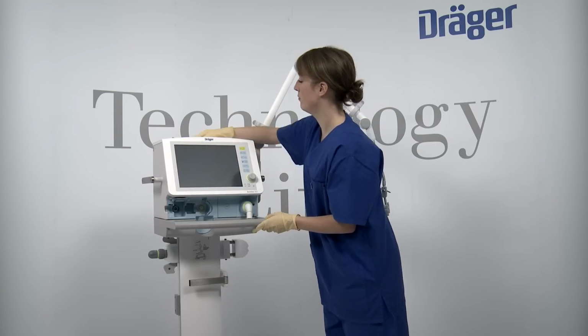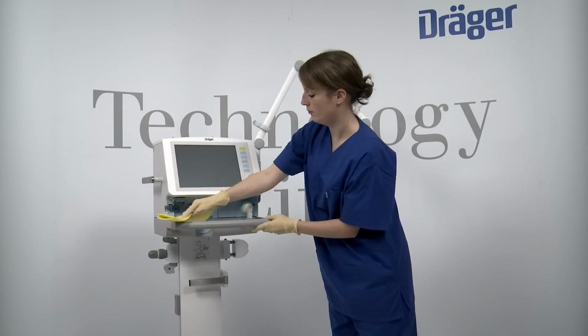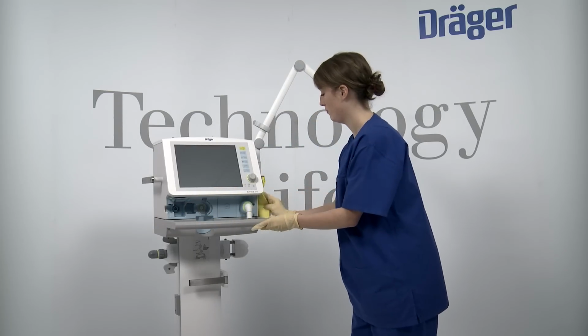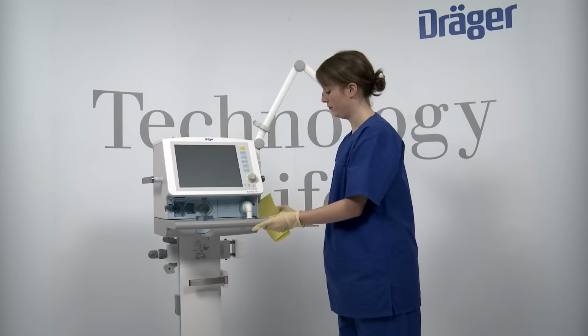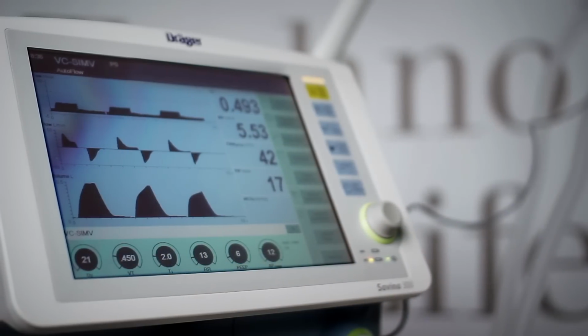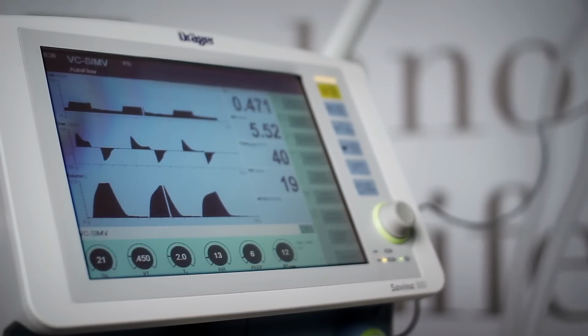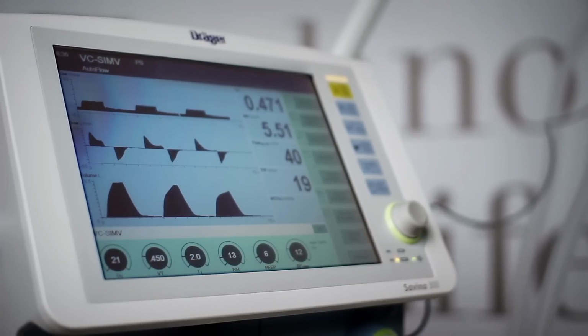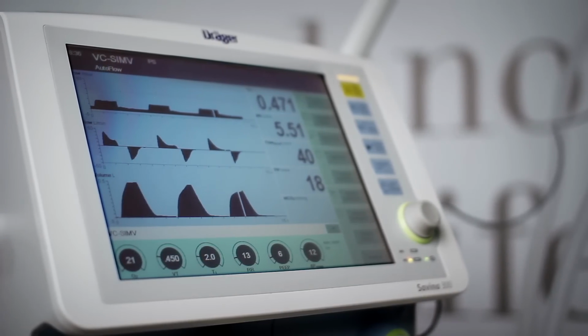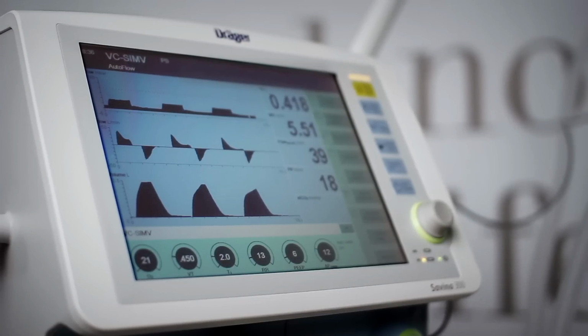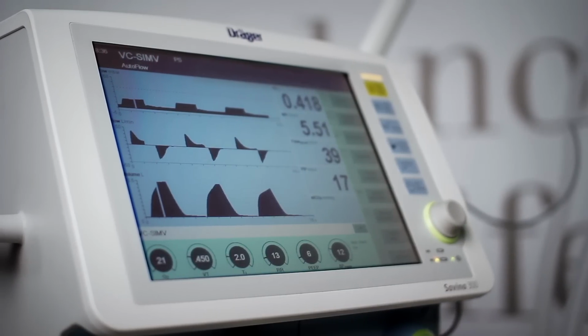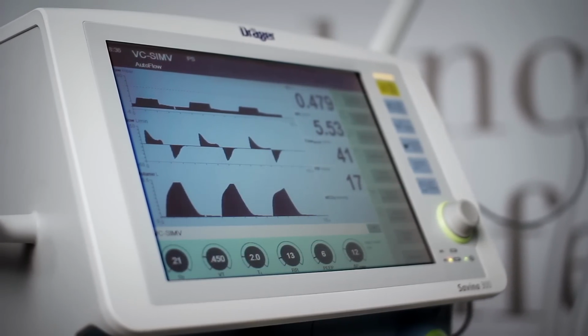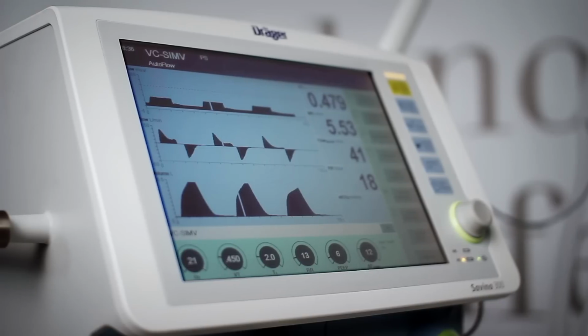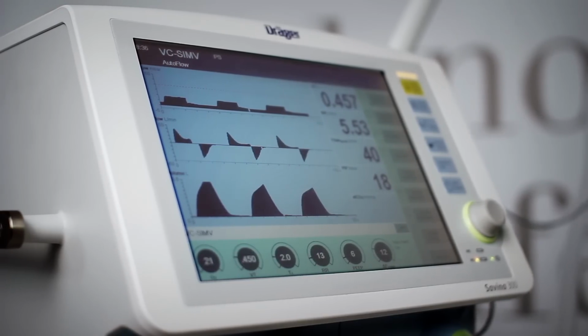Make sure that only cleaned and disinfected reusable components are sterilized. The hot steam sterilization can be performed at 134 degrees Celsius or 273.2 degrees Fahrenheit. Observe instructions for use of device. To ensure the effectiveness of sterilization, a minimum sterilization time of 5 minutes is required. You should thoroughly inspect all items for damage and wear, for example cracking, embrittlement, or pronounced hardening, and residual soiling.